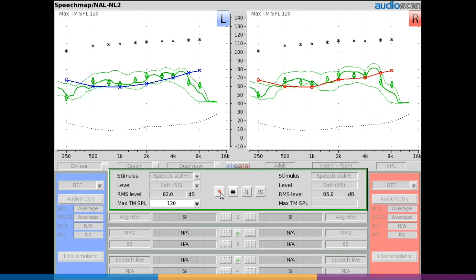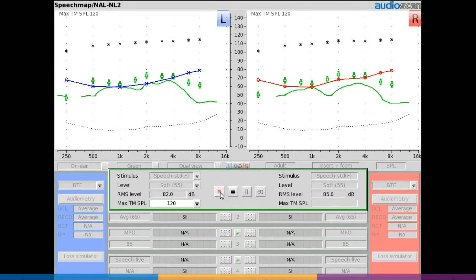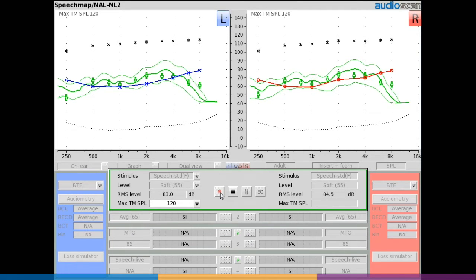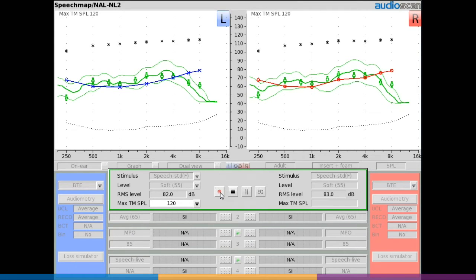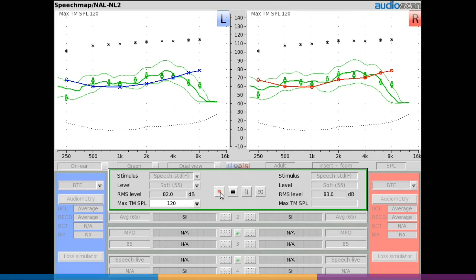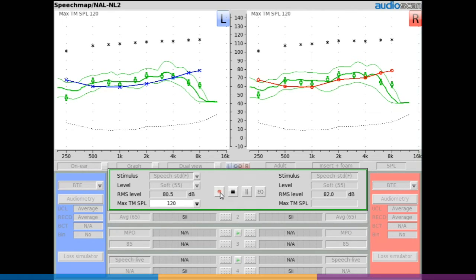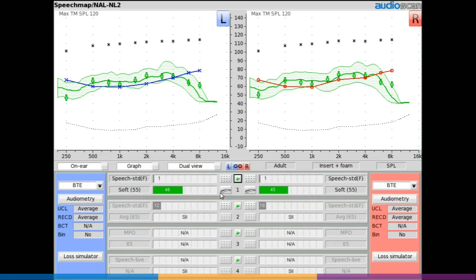Click the record button. If the sound field across ears is within 2dB overall and less than 3dB different at any single frequency, the system will complete a simultaneous binaural measurement with no further interaction.